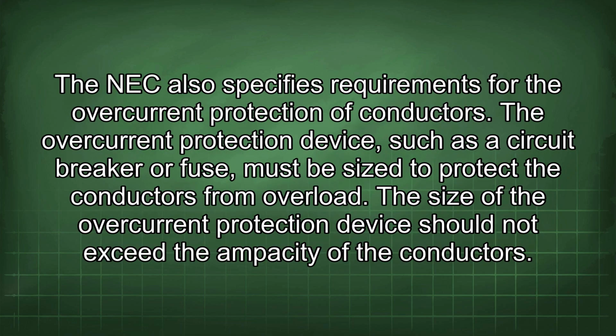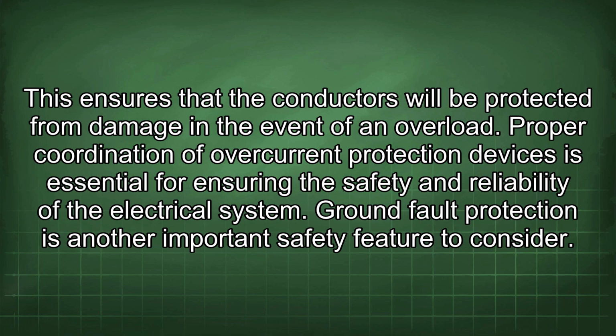The NEC also specifies requirements for the overcurrent protection of conductors. The overcurrent protection device, such as a circuit breaker or fuse, must be sized to protect the conductors from overload. The size of the overcurrent protection device should not exceed the ampacity of the conductors. This ensures that the conductors will be protected from damage in the event of an overload. Proper coordination of overcurrent protection devices is essential for ensuring the safety and reliability of the electrical system.